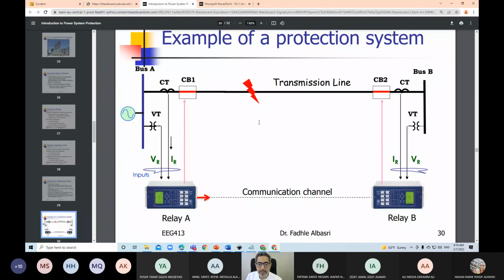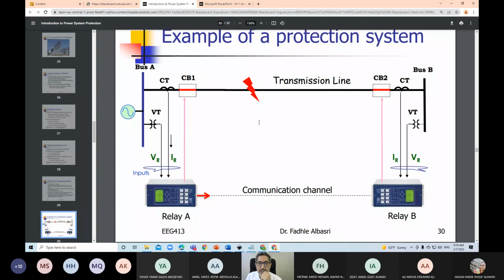So this is an example. I will conclude with this. This is an example of a protection system of a transmission line. At each end, this end could be 100 kilometers away from the other end. So when there is a fault in the transmission line, there is one relay at this end, there's another relay at the other end, and between them could be a communication channel. They can also work without communication, but generally transmission lines have communication channels in between.